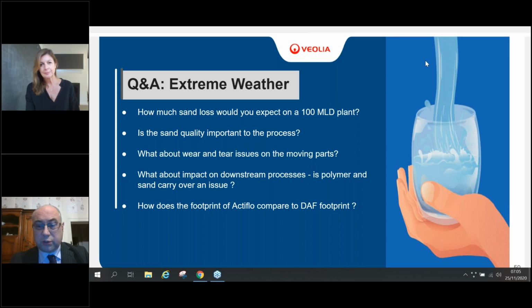The key thing is to control the dose rate and make sure it's not exceeded, so just enough is very important. Secondly, we have the antidote for this type of catastrophic event: we introduce downstream of Actiflo a very small dose of coagulant, 0.5 ppm as metal, so it's minute, almost homeopathic. This small amount of coagulant enables the residual floc to swell a little bit and therefore prevent what we call cushion fouling, a very small layer on top of filters. It's very effective and generally gets rid of the problem.